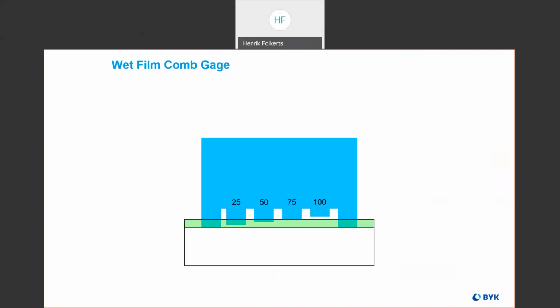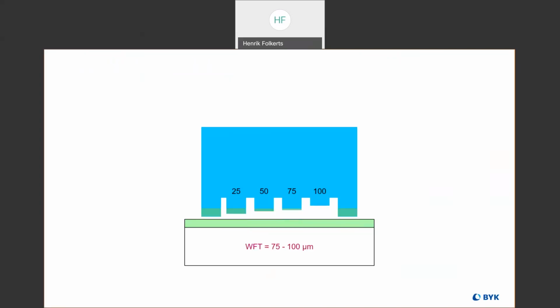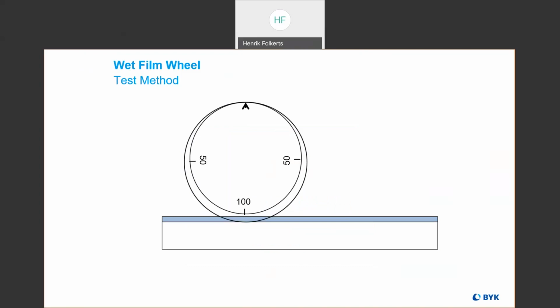So here the comb type gauge has been dipped down into the coating, and then you lift it up, and we see here that the coating has made contact with the 75 micron tooth, but not the 100 micron tooth. So we know that the wet film thickness is between 75 and 100 microns. So this is a rough tool for very roughly measuring the thickness of your wet film. And then we have the interchemical gauge, or the wet film wheel, as it's commonly called. And this is a bit more precise.